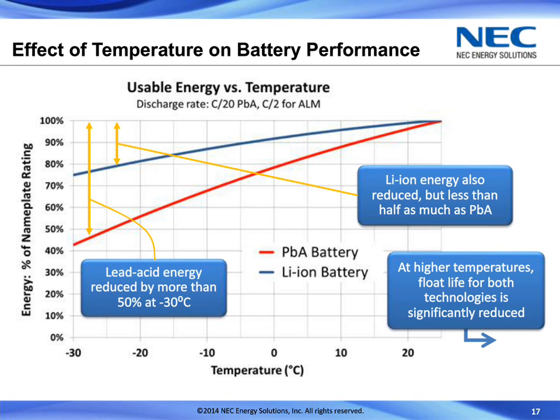So if you're going to use a lead acid battery and not provide any kind of heating for that battery, you're going to have to oversize your system and plan for less than 50% of that capacity, not even including the capacity issues associated with the discharge rate that we talked about earlier. You have to plan for more than 50% of that capacity to not be available to you.